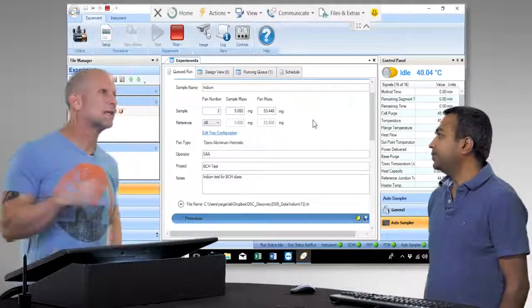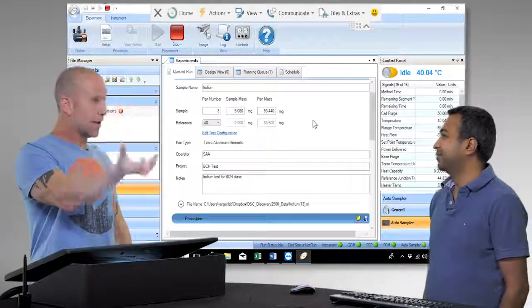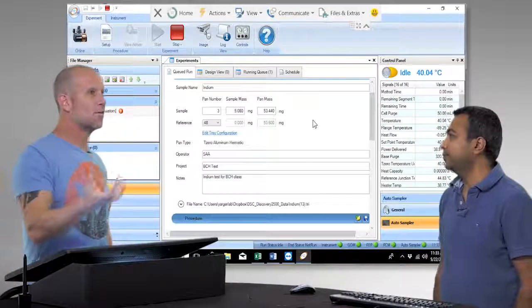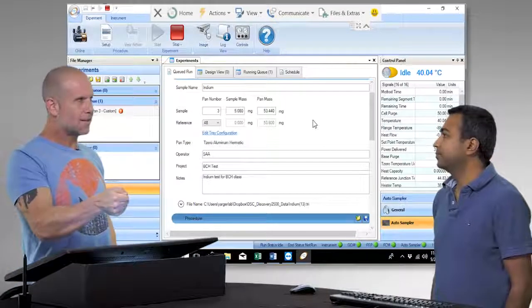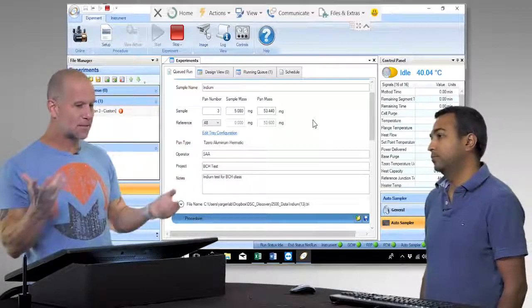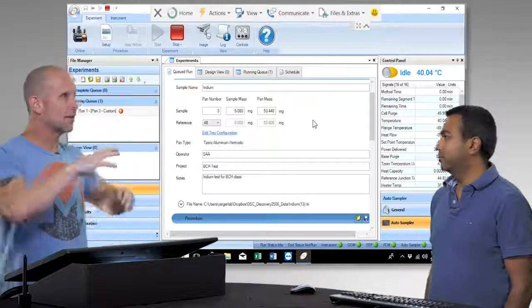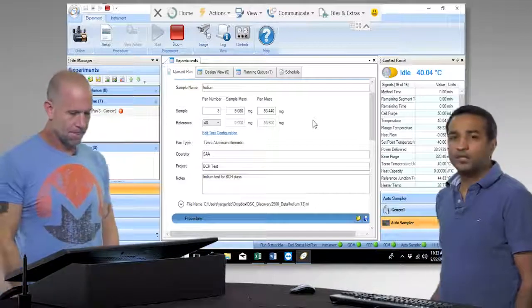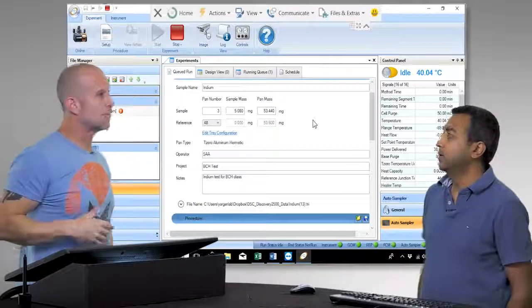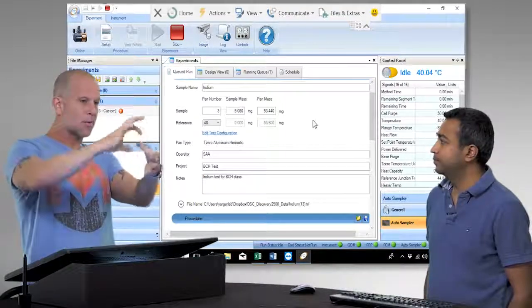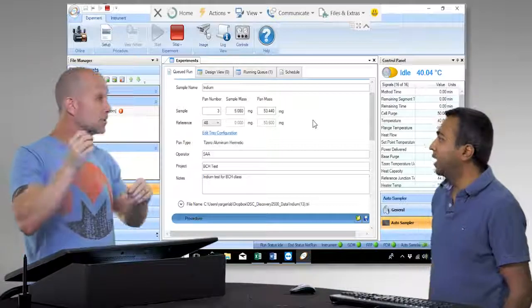The hermetically sealed aluminum and the crimp-style aluminum are the two most popular. I always like hermetic because you know things can't get into or out of the system — both from a care-of-the-DSC standpoint. As long as you've leak-tested that hermetic seal, weighed it, and re-weighed it after putting it in an oven at the maximum temperature, you know nothing got out. The crimp style typically gives better data because you have better thermal conductivity to the sample, which can often be really critical.